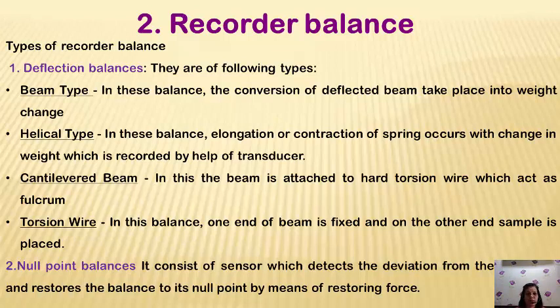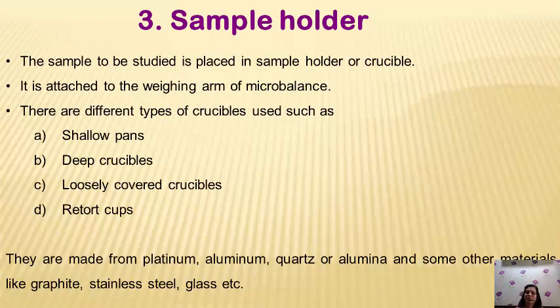Initially there were deflection balances, like a regular pan balance. Then balances with a string attached and a pan were used, showing the change in weight on the right-hand side. The null point balance shows deflection in weight and comes back to zero. Sample holder types include shallow open pans, deep crucibles, and loosely covered crucibles — where the lid is loosely covered so that gas released during heating can easily escape. Retort cups are compact containers.